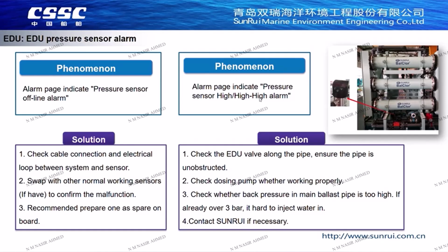In case of high alarm, check whether the EDU pipeline is unobstructed or the dosing pump works normally. Also pay attention to the pressure of the main pipeline. If the back pressure of the main pipe has exceeded 3 bar, it may be difficult to inject EDU seawater into the main pipeline due to the capacity limitation of the dosing pump, which may happen when the buffer tank is almost full.